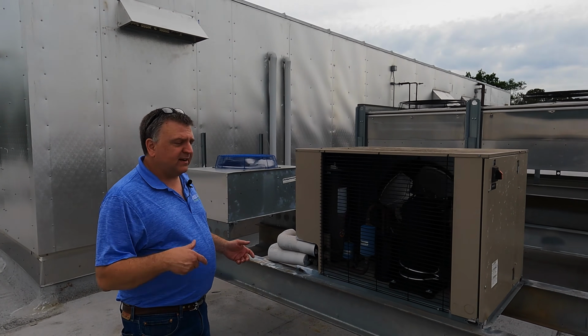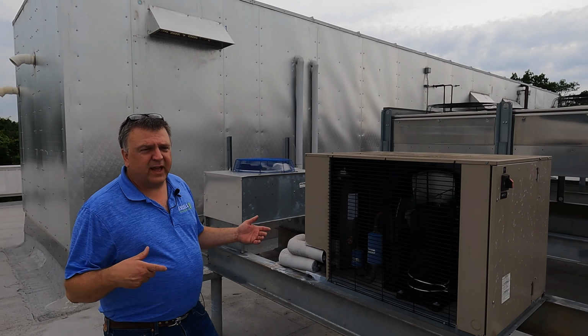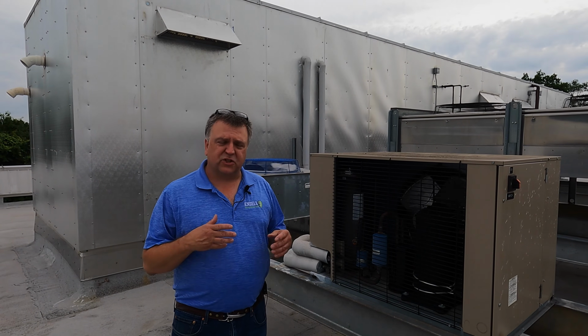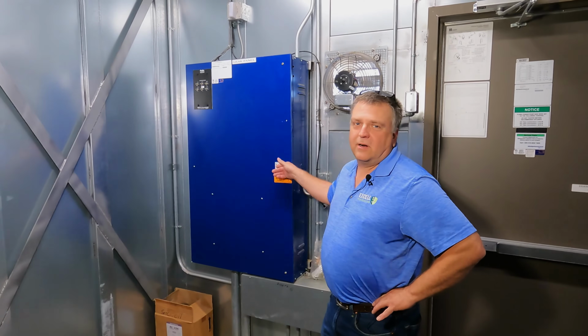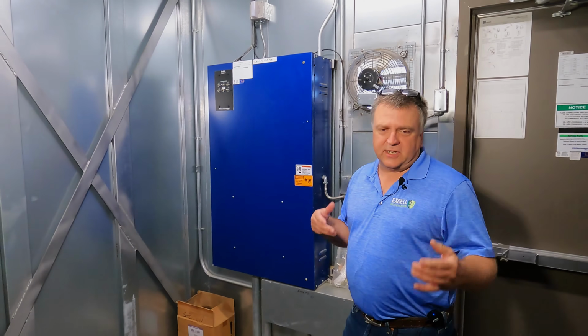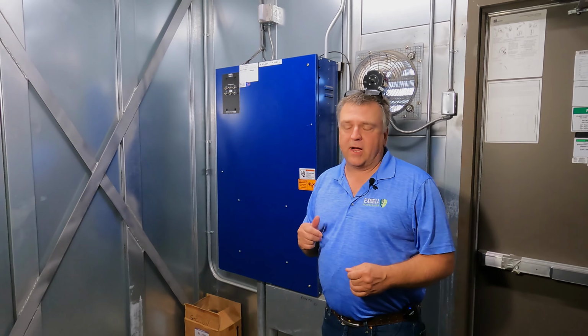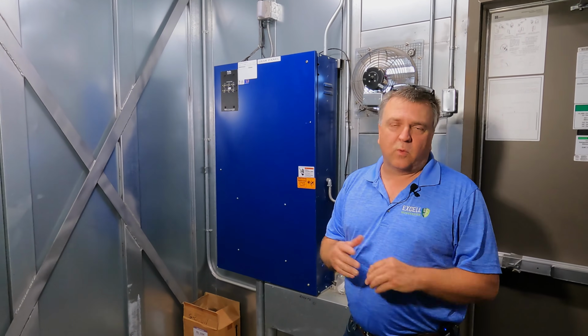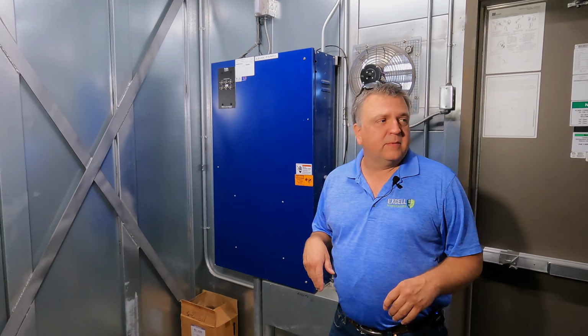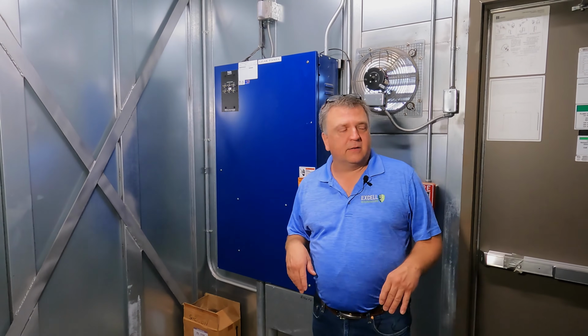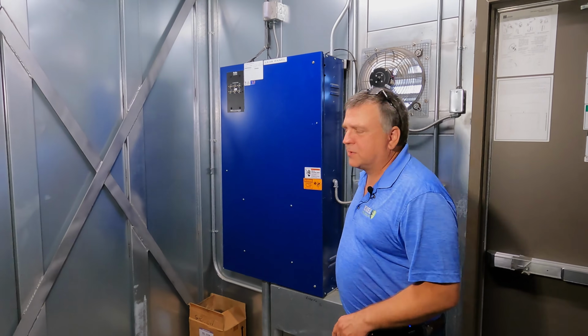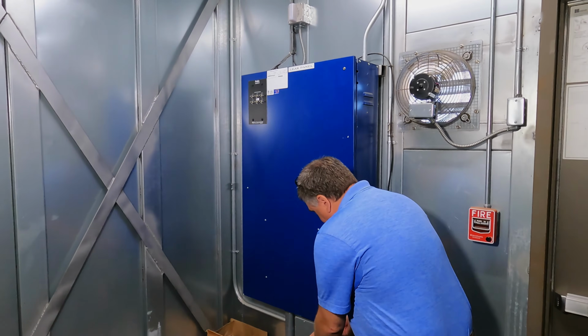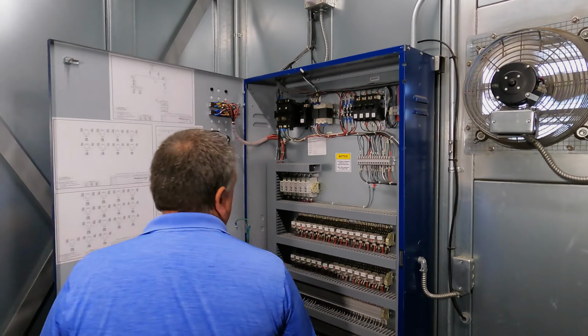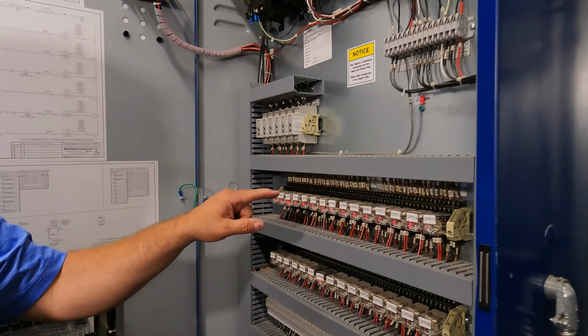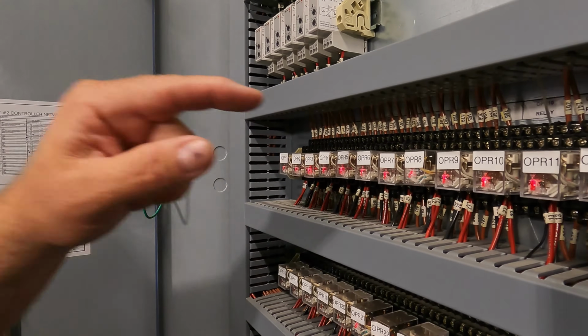Now, with that being said, if something fails in the rack, we have something called a critical alarm that's going to shut all of our cases down. This is our alarm panel. We're going to use a scenario, say the power's been out for 4 hours. All that CO2 is warm, we need to bring it back up. The rack's going to come back on. The first thing that's going to happen is we're going to de-energize a bunch of relays. These are known as our overpressure relays.